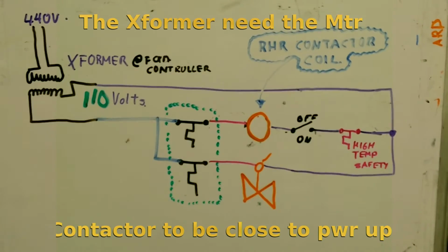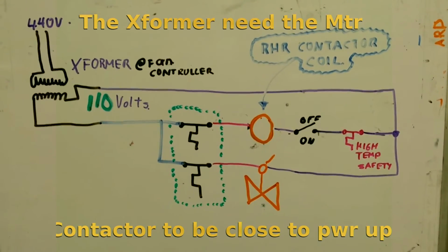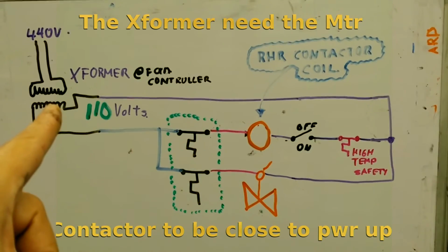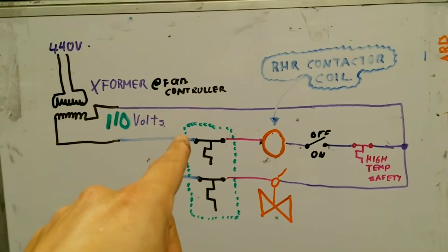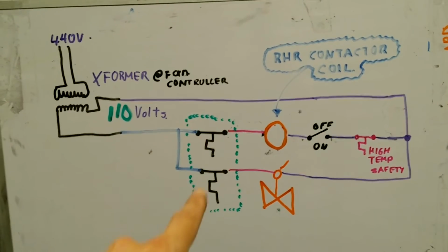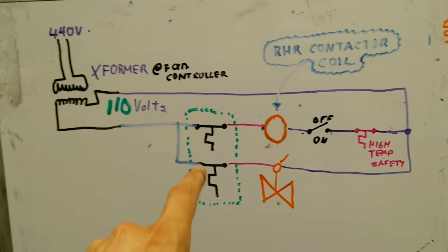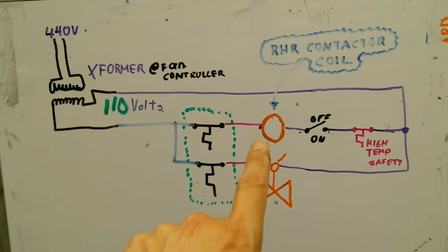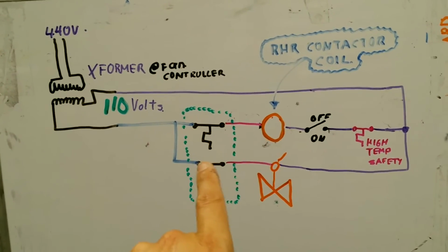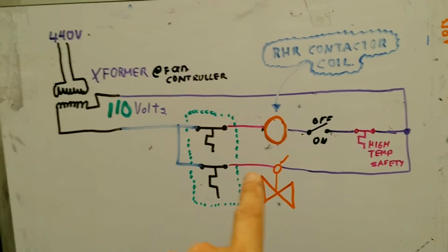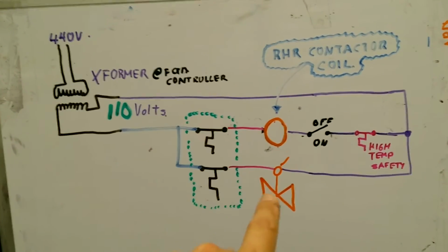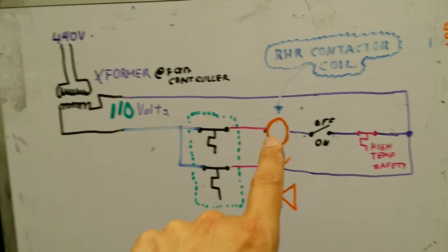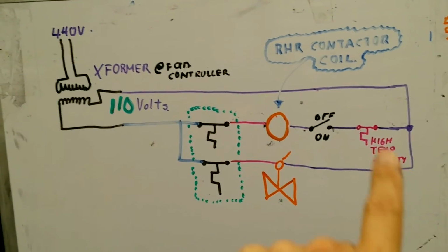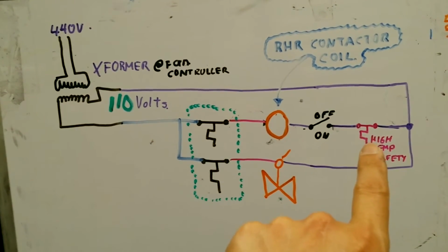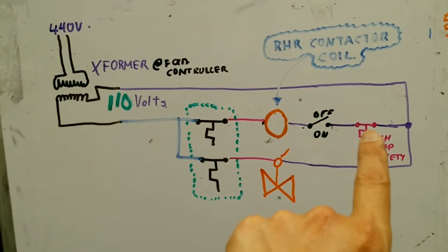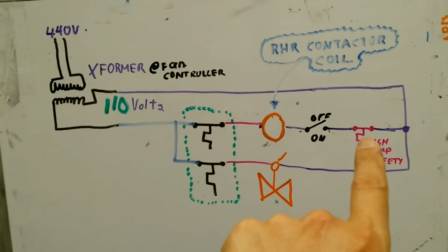Alright, so I know I already talked about this, but I just want to make sure that it's very clear that the transformer is located at the fan controller, and it gives control power via the thermostatic switch, and the thermostatic switch controls both the reheater contactor coil and the solenoid valve. So in that way, it has the power to decide if it's time to cool or if it's time to heat up as needed. And this is a high temperature safety thermostat that is actually located inside of the reheater itself.